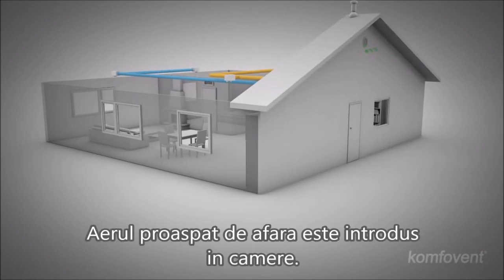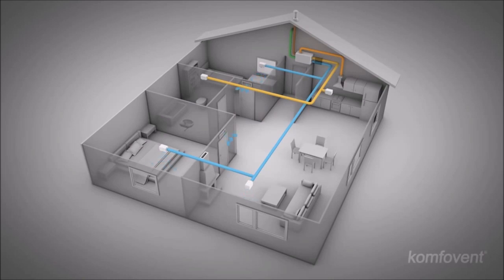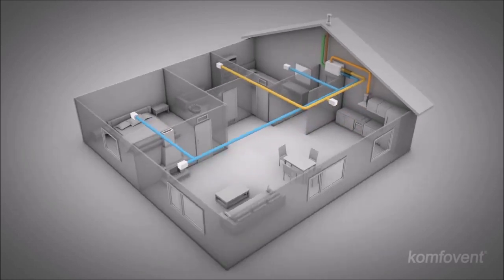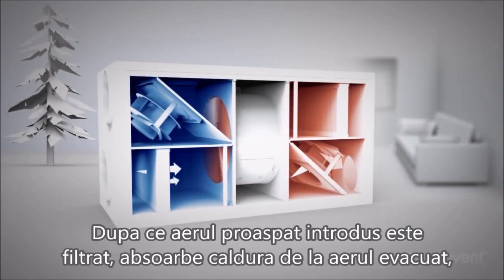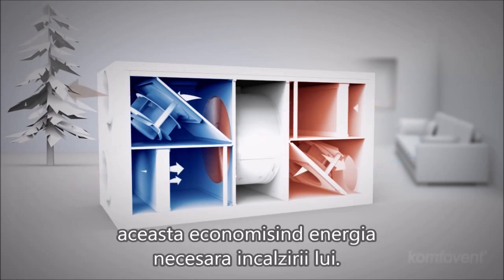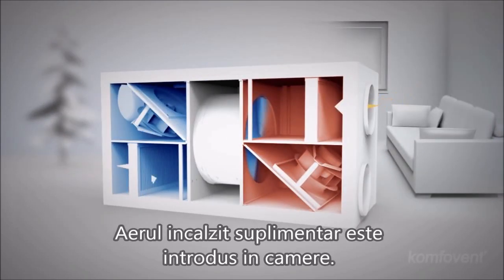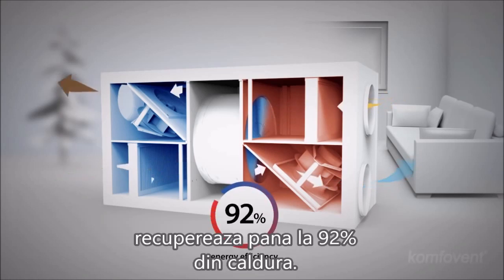Fresh air from outside is drawn into the rooms. Contaminated air is drawn from the rooms and vented to avoid mixture with the incoming air. After the incoming fresh air is cleaned, it absorbs heat from the vented air, thus saving energy required for air heating. This is called heat recovery. Additional heated air is supplied to the rooms. The innovative rotary heat exchangers used in Komfovent ventilation units recover up to 92% of heat.